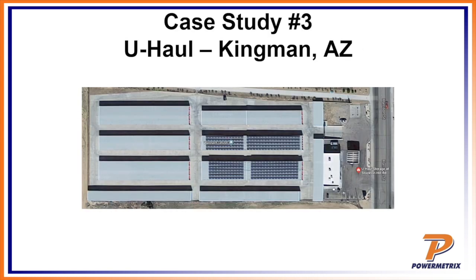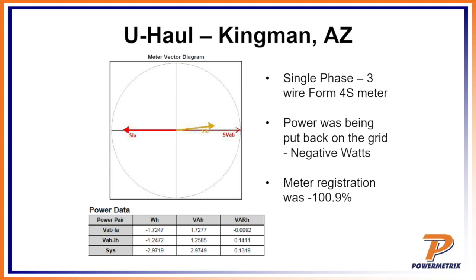Another one, this was a U-Haul out in Kingman, Arizona. Solar panels, similar situation. This was a single phase three wire using a form 4 meter. If you look at where A and B are, they're swapped, right? So you've got generation mode, and when we ran a customer load meter test, we actually got a negative registration, which is correct.